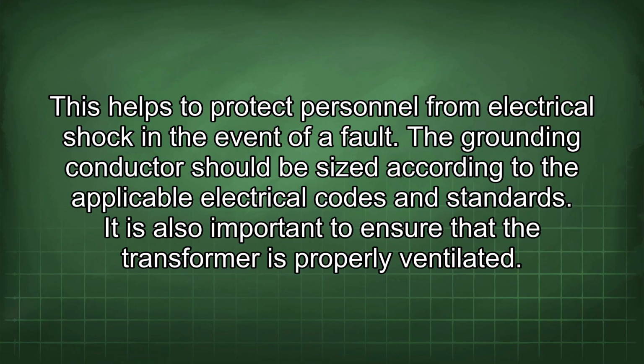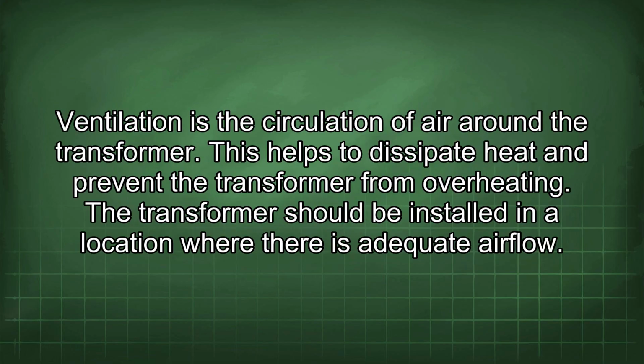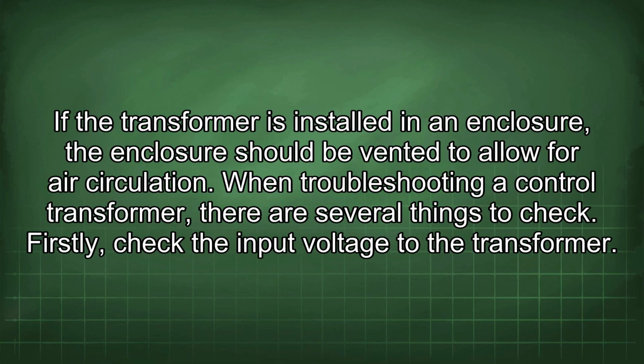It is also important to ensure that the transformer is properly ventilated. Ventilation is the circulation of air around the transformer. This helps to dissipate heat and prevent the transformer from overheating. The transformer should be installed in a location where there is adequate airflow. If the transformer is installed in an enclosure, the enclosure should be vented to allow for air circulation.